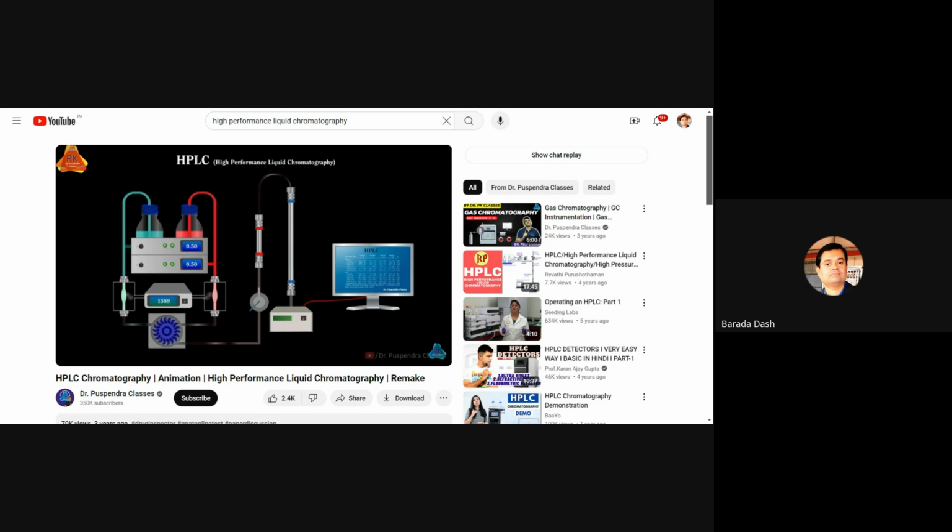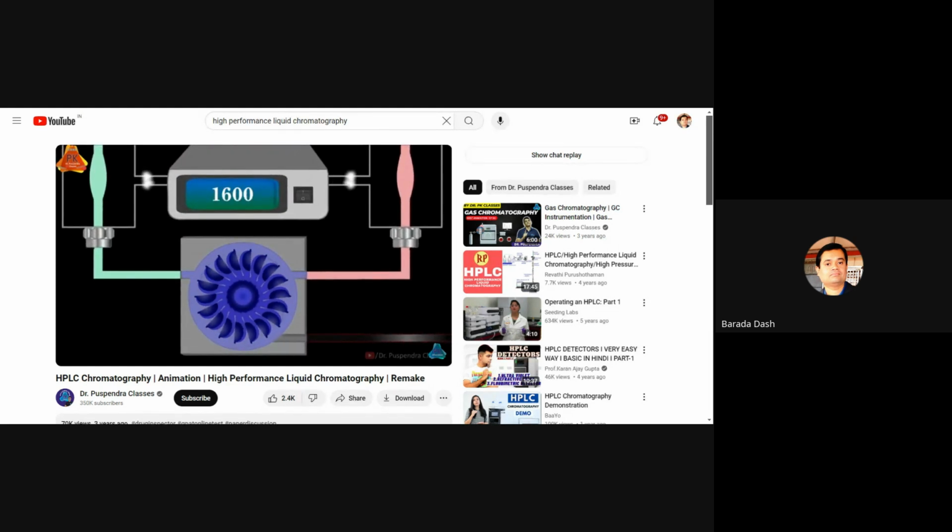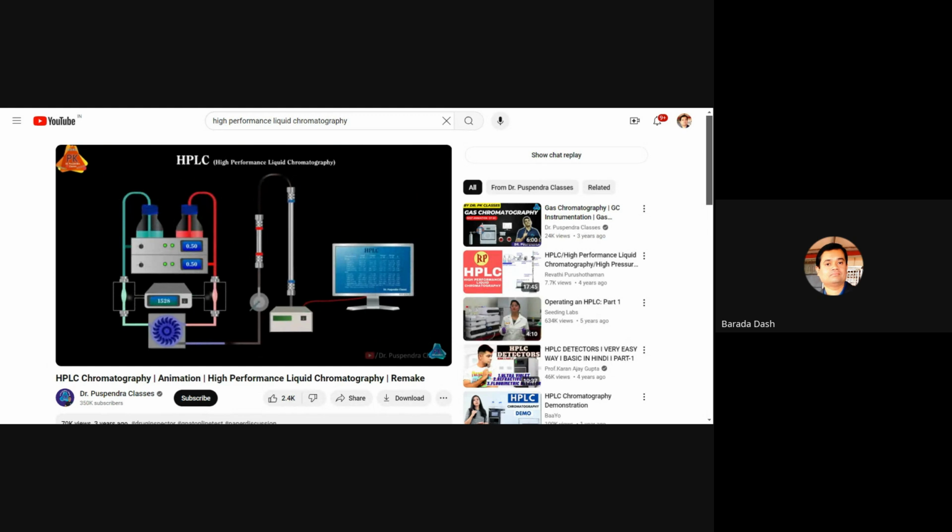because this may create problem during elution. After degassing, solvents of the mobile phase will move towards the solvent mixing valve, and mixing of the solvents take place, which will help to produce uniform mobile phase. Now this mobile phase will run towards the pre-column or guard column. This guard column will remove any kind of impurity present in the mobile phase and protects analytical column from the impurities. In the next step, mobile phase will further move towards the analytical column, then finally goes to detector.